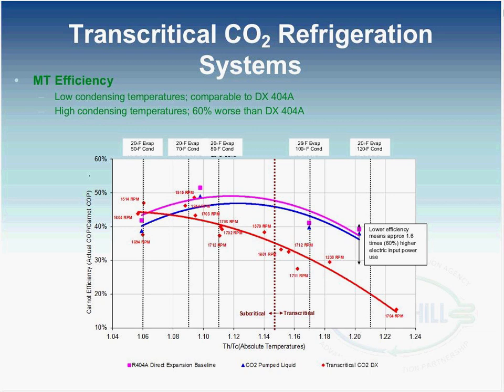You see that vertical line that has subcritical to the left and transcritical to the right. That's where the CO2 system starts working above that critical point that we looked at earlier in that dome. So out in that range, we find that the system is less efficient than the other systems, by about 60% relative to a medium temp system. And again, medium temp would be your fresh foods, dairies, delis, things of that nature, food products that are not frozen.